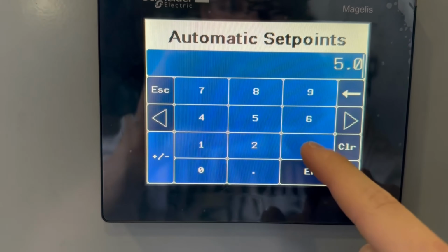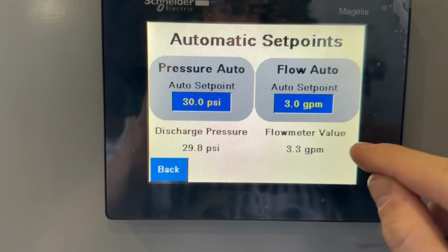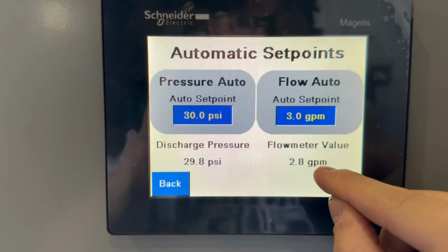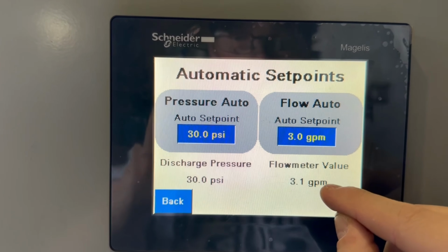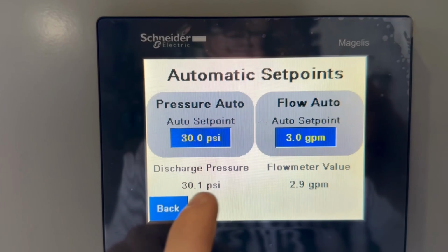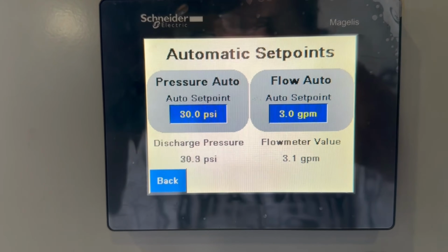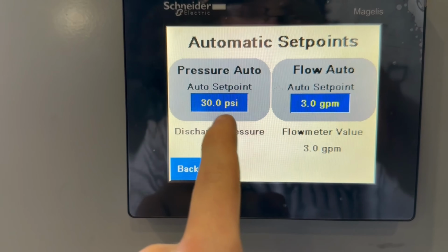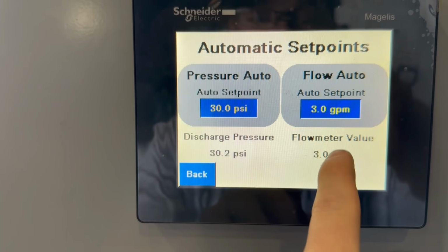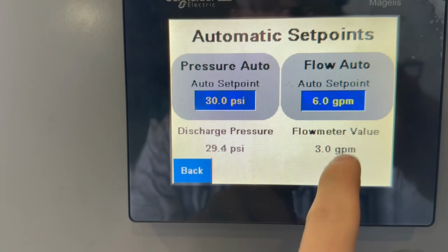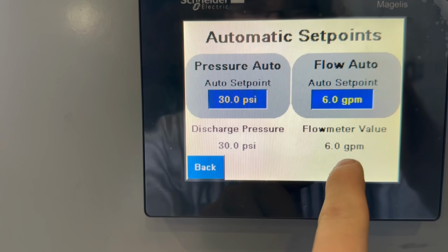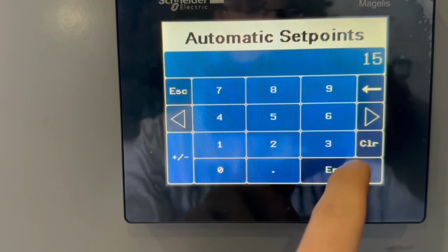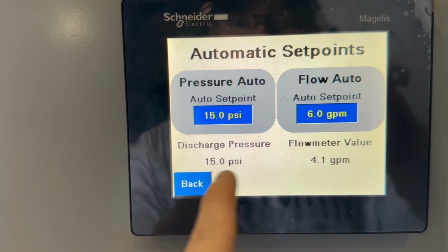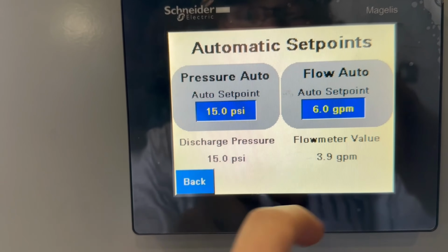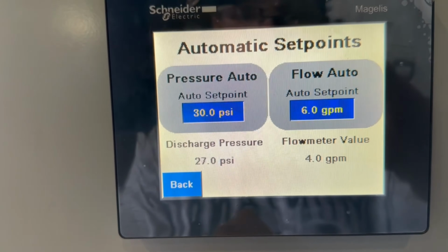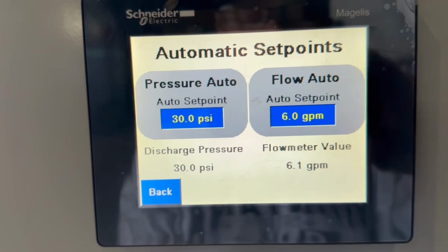Now, if I wanted to change this to 3 gallons a minute, I'll enter 3 here, and that valve will close, and then it'll slowly bring it back up. Small amount of oscillation, not too much to worry about, but we're maintaining our 30 psi with 3 gallons a minute. Now there is a quirk with this, that if I wanted to set the psi low enough that the valve would not be able to keep up, so say 6 gallons per minute here, we can keep it at 6 gallons a minute, but if I decrease the pressure it's not going to be able to keep up. We can maintain pressure, but we won't be able to maintain flow. Now, if we put that back up, obviously it will be able to maintain that gallons per minute.